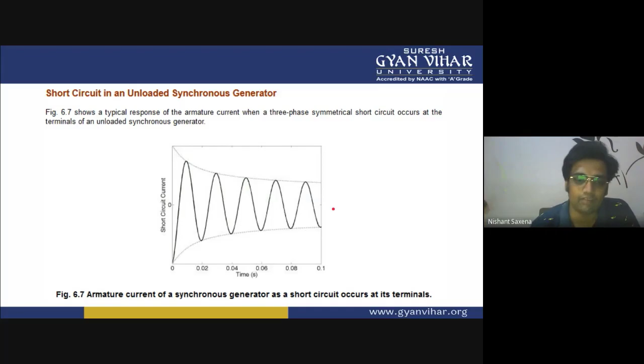Now, when a short circuit occurs on an unloaded synchronous generator, how does the armature current of the synchronous generator behave? Look at this. This is the typical response of an armature current when a three-phase symmetrical short circuit occurs at the terminals of an unloaded synchronous generator. The synchronous generator is not loaded. It is not supplying any electrical power to the system, but it is consistently running. When a short circuit occurs, we can see that the DC component and AC component are both present in the system. We have two envelopes: one is the DC component envelope and the other is the AC component envelope. The DC is the decaying part, and the AC is first higher, then it follows its own envelope.